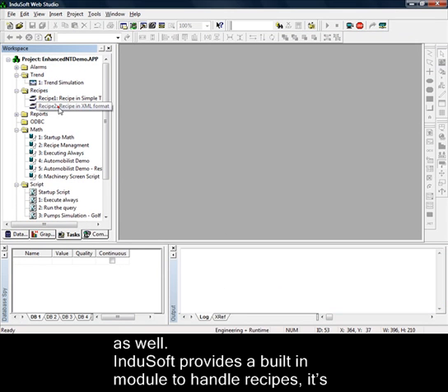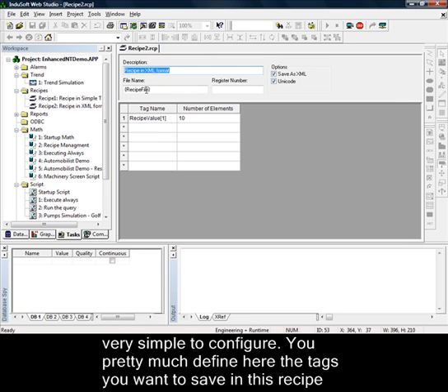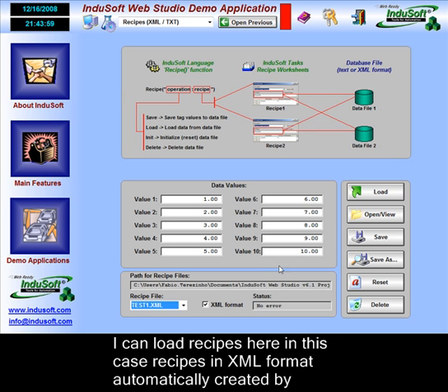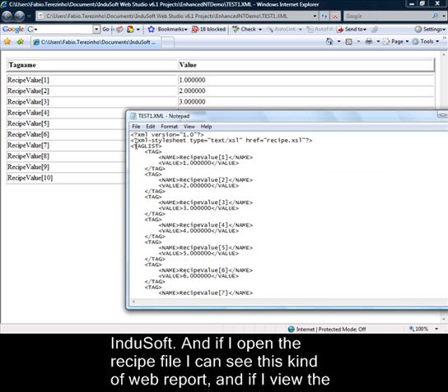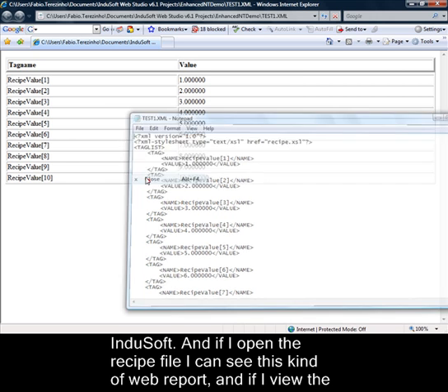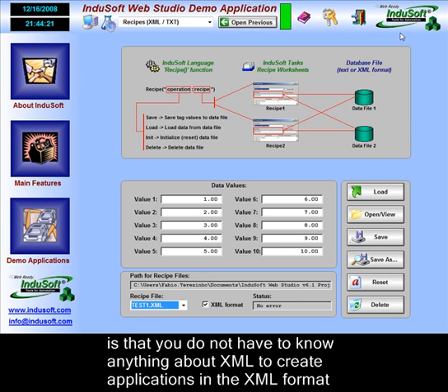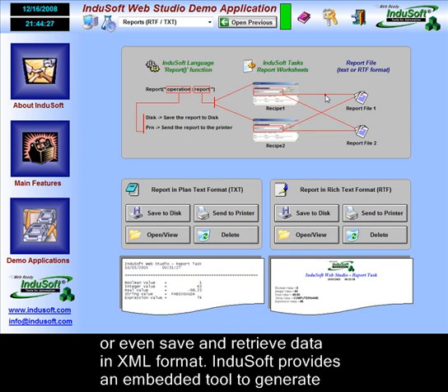Indusoft provides a built-in module to handle recipes. It's very simple to configure — you define the tags you want to save in the recipe and the recipe name, which can be changed dynamically during runtime. During the runtime, I can load recipes — in this case, recipes in XML format automatically created by Indusoft. If I open the recipe file, I can see a web report, and if I view the source, it's an actual XML file automatically created by Indusoft. The main advantage is that you do not have to know anything about XML to create applications that save and retrieve data in XML format.